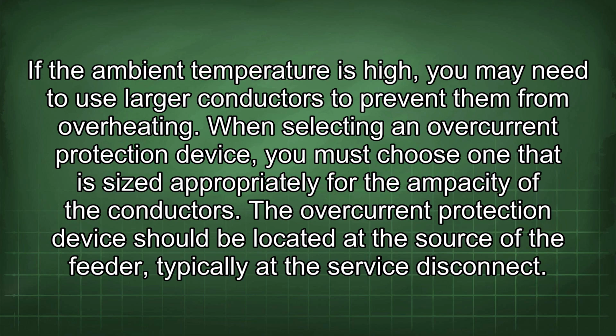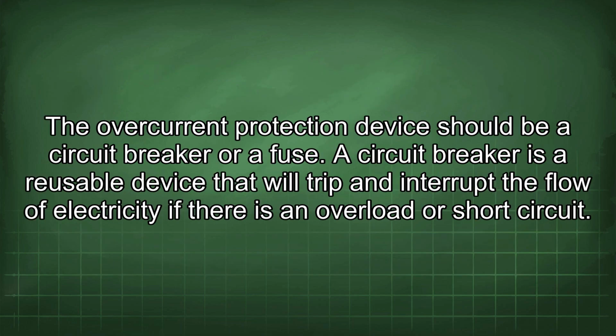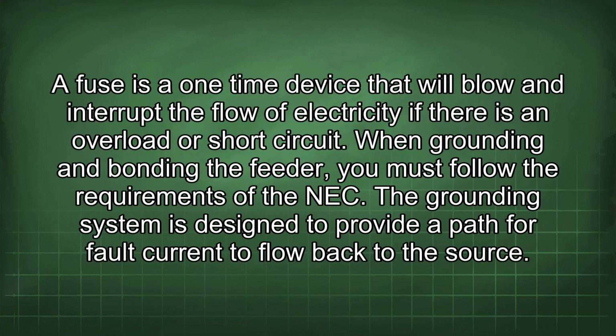When selecting an overcurrent protection device, you must choose one that is sized appropriately for the ampacity of the conductors. The overcurrent protection device should be located at the source of the feeder, typically at the service disconnect. The overcurrent protection device should be a circuit breaker or a fuse. A circuit breaker is a reusable device that will trip and interrupt the flow of electricity if there is an overload or short circuit. A fuse is a one-time device that will blow and interrupt the flow of electricity if there is an overload or short circuit.